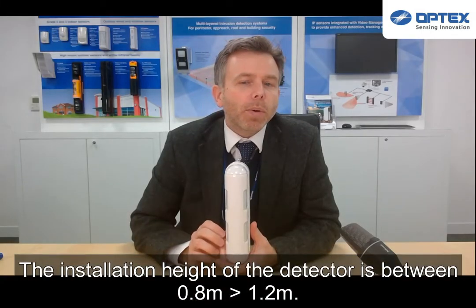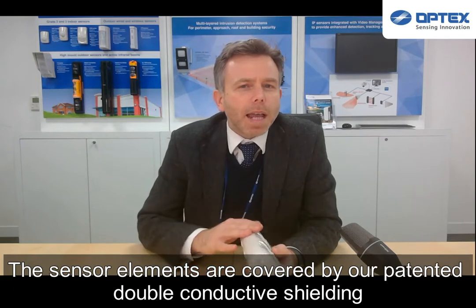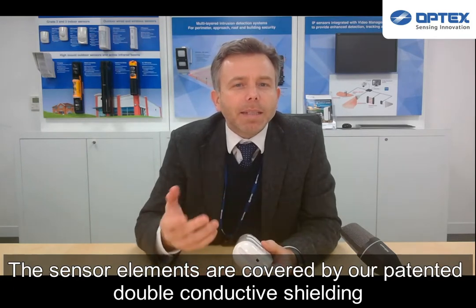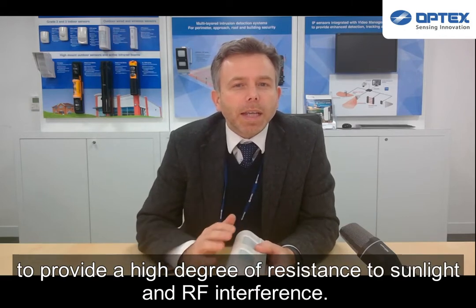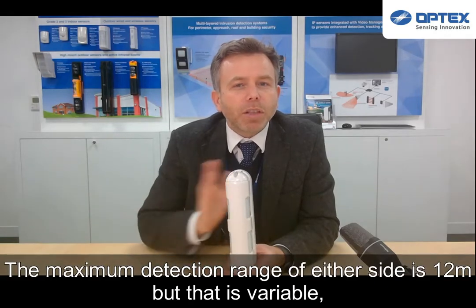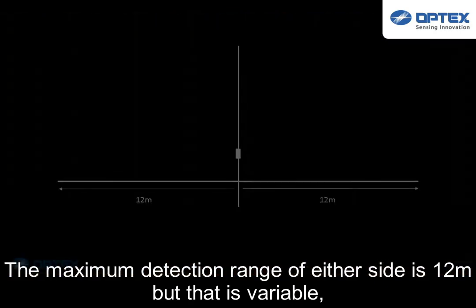The installation height of the sensor is between 0.8 and 1.2 meters. The sensor elements are covered by our patented double conductive shielding to provide a high degree of resistance to sunlight and RF interference. The maximum detection range on either side is 12 meters.